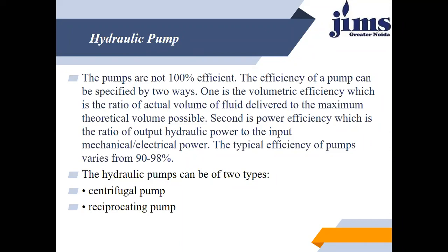I already told you in the previous class about this. The hydrodynamic or non-positive displacement type of pumps is used in low pressure, high volume flow applications. Just keep that in mind, this is very important. A centrifugal pump is applicable for low pressure, high volume flow applications. And secondly, I told you about the hydrostatic or positive displacement pump.